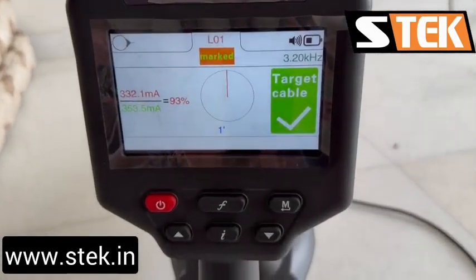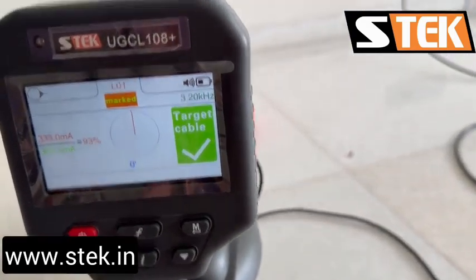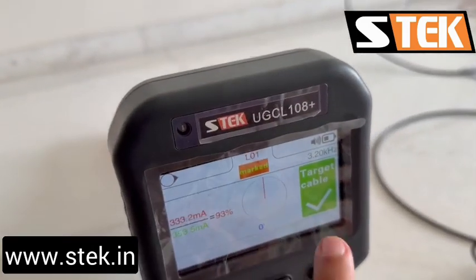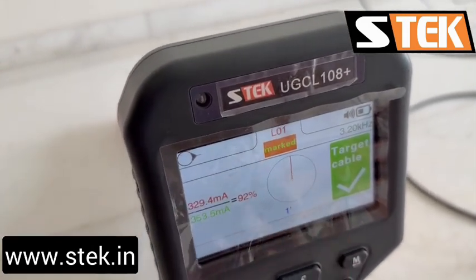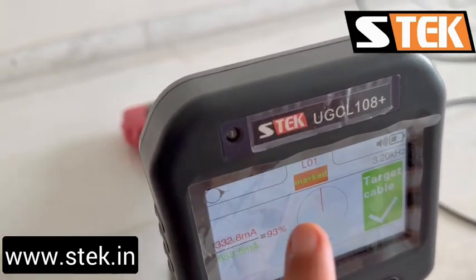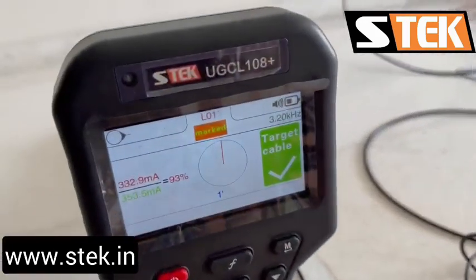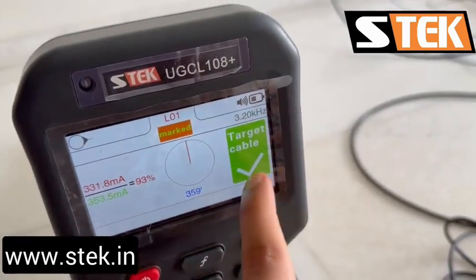And as you can see, it shows as target cable. This green value, the phase, is what it expects it to be, and the percentage is close to 100. These are the two factors it uses to identify whether it's a target cable or not.